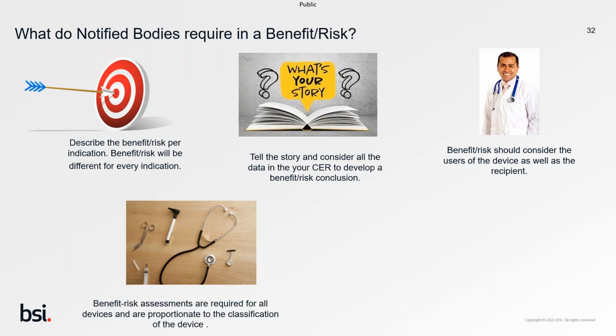Also, a benefit risk assessment is required for all devices and can be proportionate to the classification of the device. Whilst we saw on the other screen a basic syringe, for example, a benefit risk assessment there is going to be quite limited because there is limited benefit and very small risks. But when you start to talk about more complex, class 3 implantable devices, the notified body is looking for a good, clear argument for those points that we've mentioned.